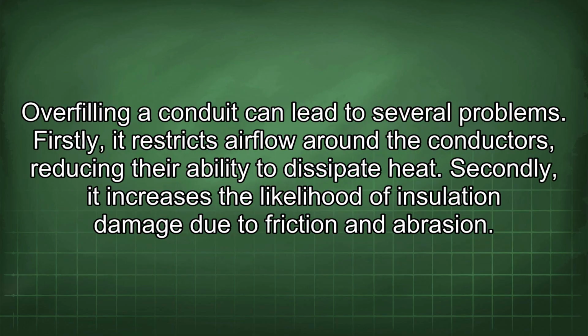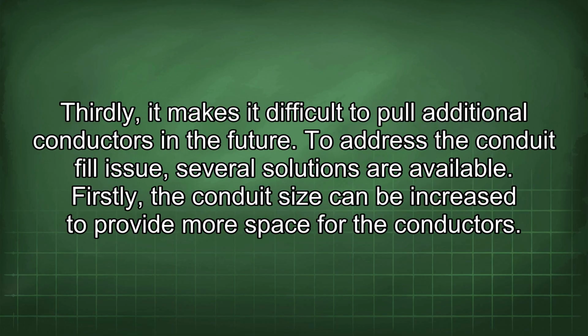Overfilling a conduit can lead to several problems. Firstly, it restricts airflow around the conductors, reducing their ability to dissipate heat. Secondly, it increases the likelihood of insulation damage due to friction and abrasion. Thirdly, it makes it difficult to pull additional conductors in the future.